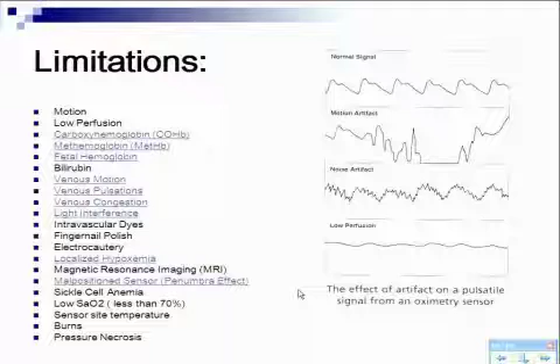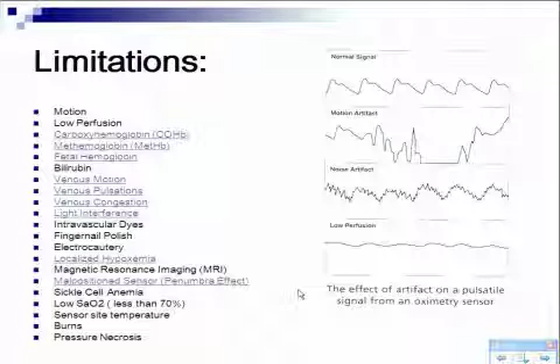You can see this kind of waveform from low perfusion. With MRI you have to use a specialized pulse oximeter in an MRI scanner, otherwise it goes flying. Not something you want to do. Malposition, which is actually a penumbra effect, which I was explaining before. Sickle cell anemia will also give you problems with readings. Of course, pressure necrosis can occur with pulse oximetry, especially the ones that look like clips. So we've got to be careful with them. Okay? Any questions?